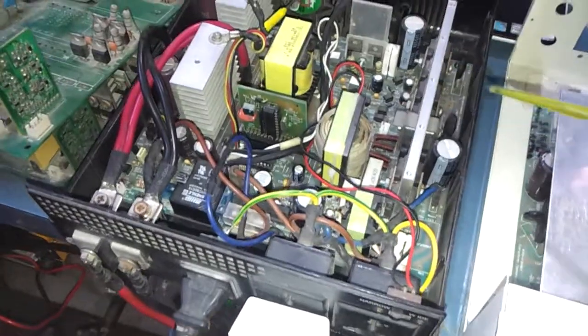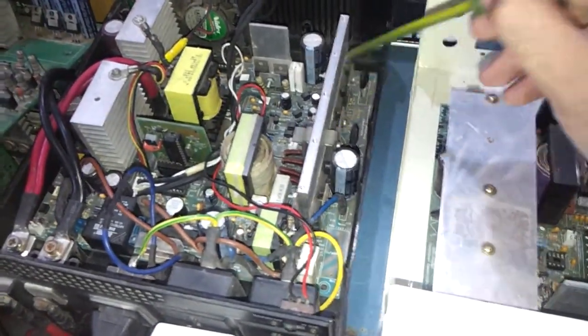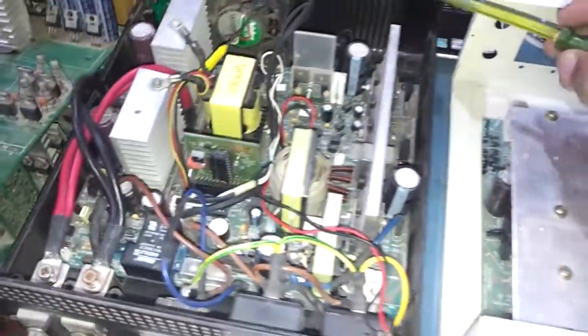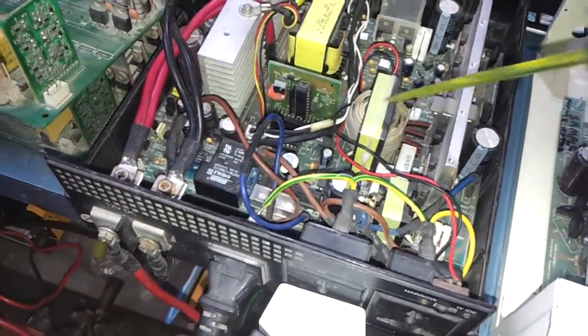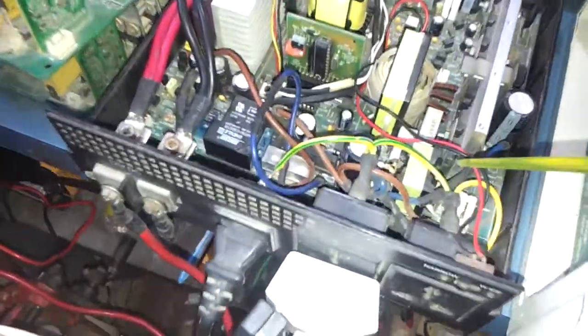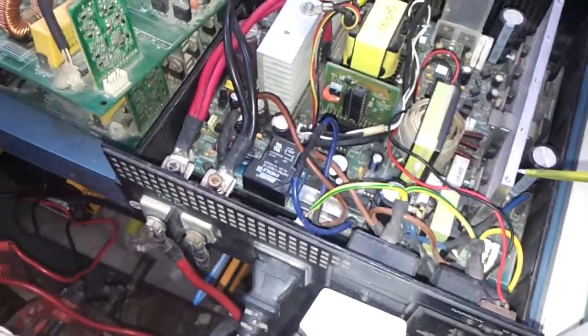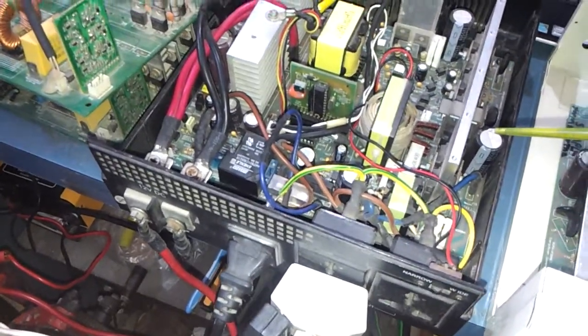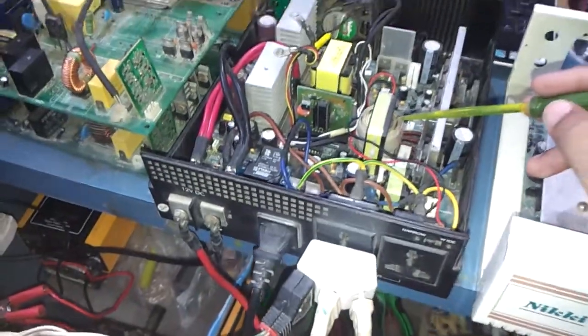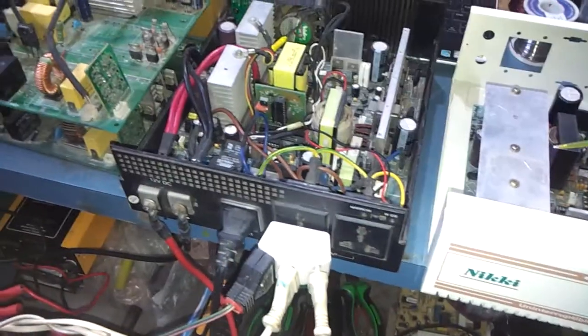The 50 Hz AC output is made by this third inverter, which is transformerless, and the battery charging DC current is produced by these Schottky rectifiers. The charger is capacitive coupled half bridge, unlike the flyback in commonly imported UPSs of this type. This is in order to have better utilization of transformer, simplify transformer design, and to relieve flyback high voltage stresses on the power MOSFETs by lowering the maximum drain source voltages, thereby reducing warranty cost.